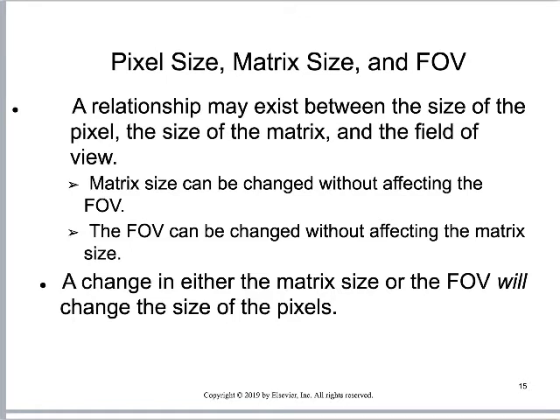It's a fairly complex relationship, but basically a matrix size can be changed without affecting the field of view, and a field of view can be changed without affecting the matrix. What changes is the size of the pixels. If we increase the matrix size, the pixels decrease in size. If we increase the field of view while keeping the matrix the same, the pixel size would have to increase — so by increasing the field of view, we would have a decrease in spatial resolution.